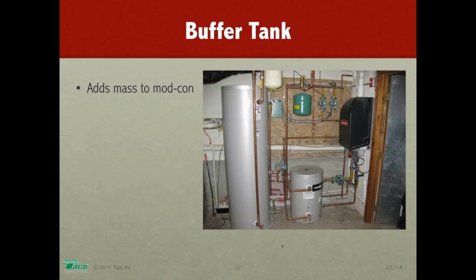Short cycling kills ModCon boilers. It's one of those things. It's like a time bomb out there. The way we've piped them up traditionally, we are encouraging them to short cycle. And short cycling is never as efficient as it could or should be, and the more it short cycles, the faster we tend to wear out important, expensive components in the system that are going to need to be replaced.